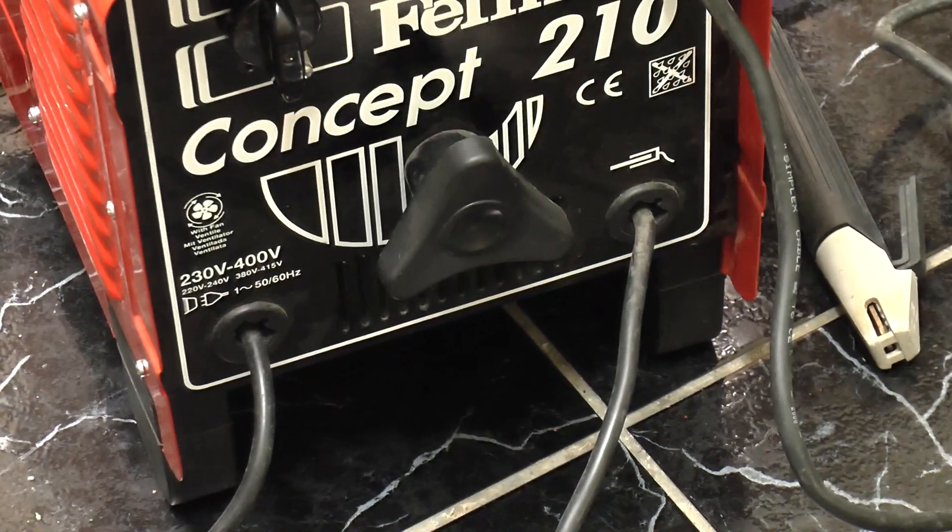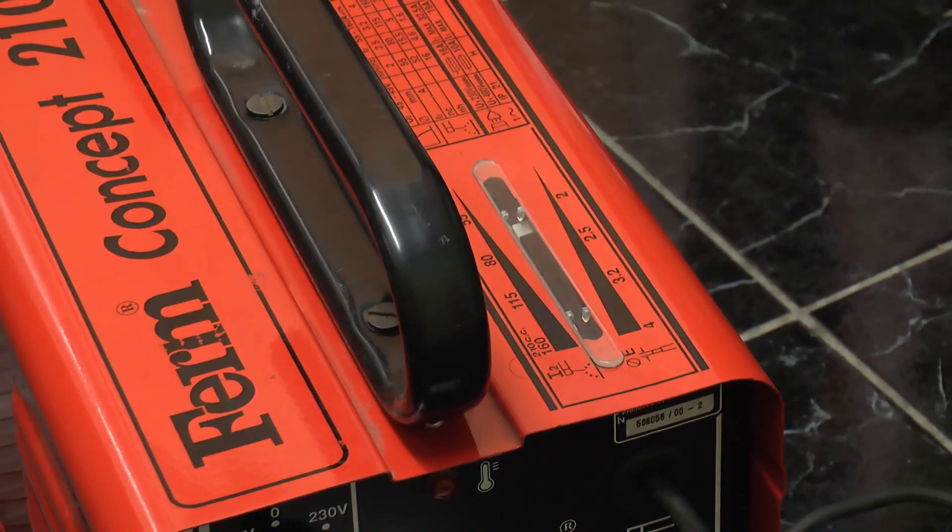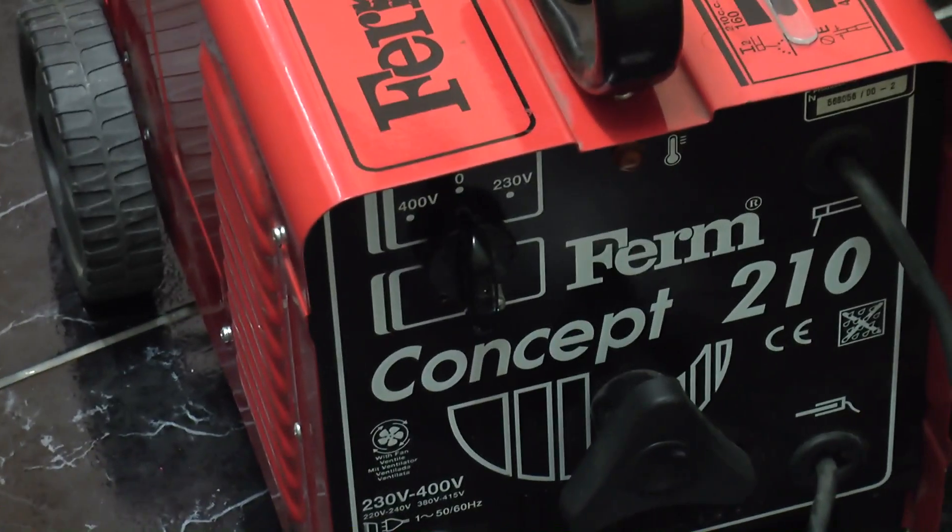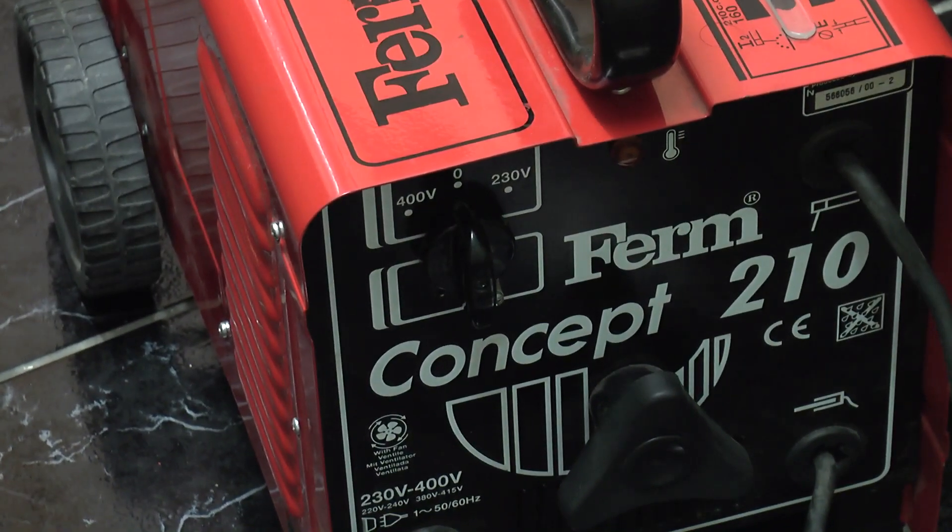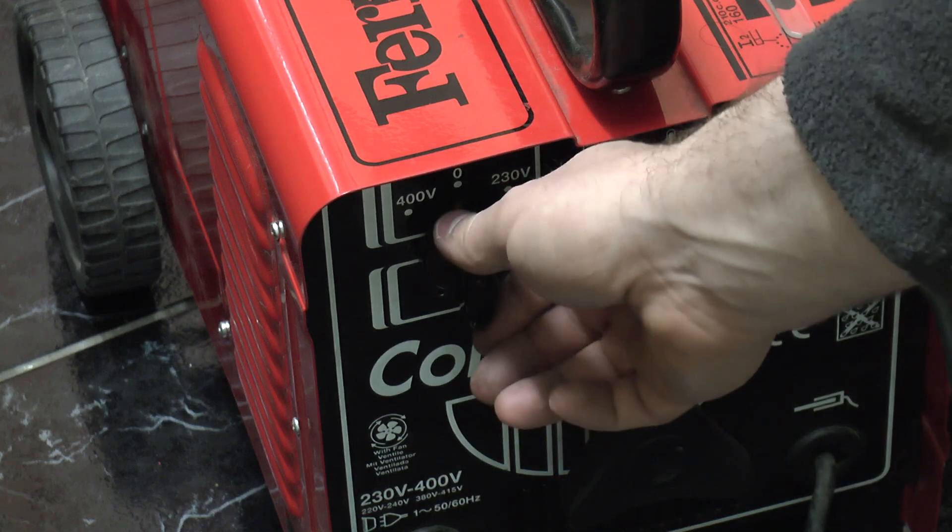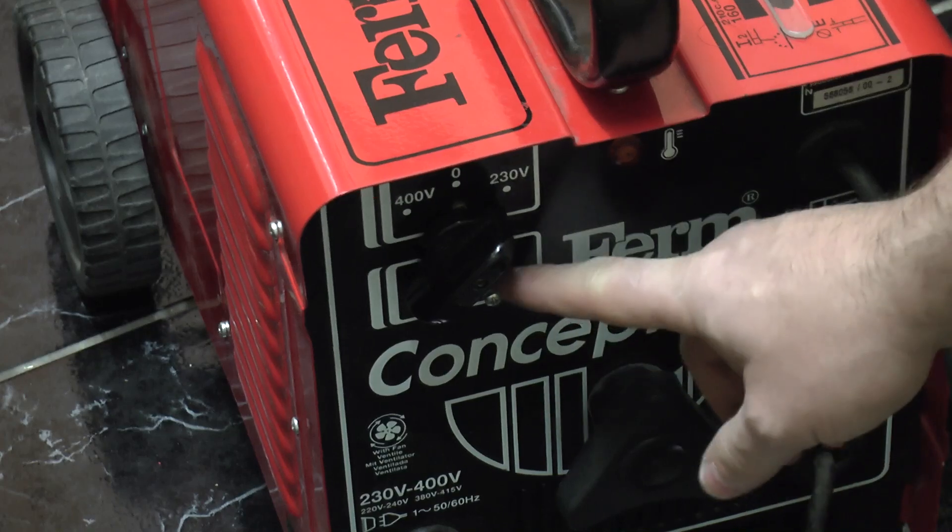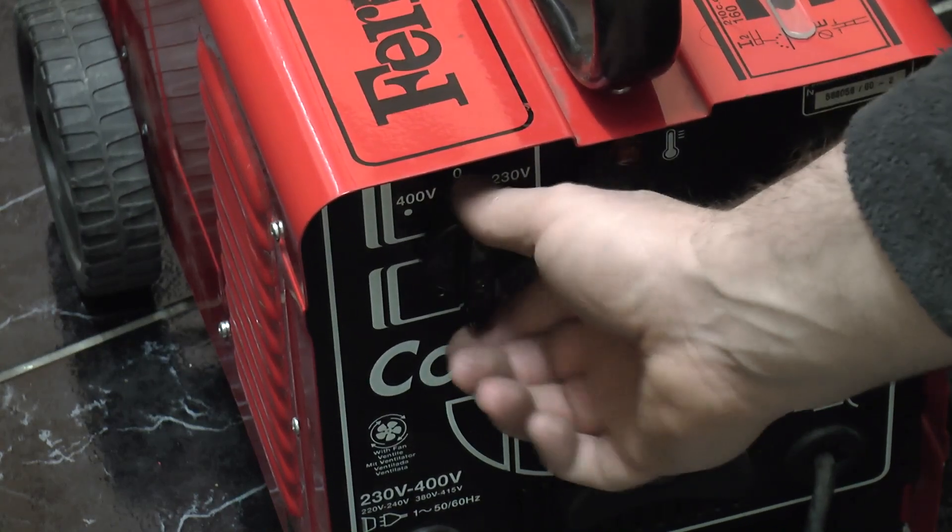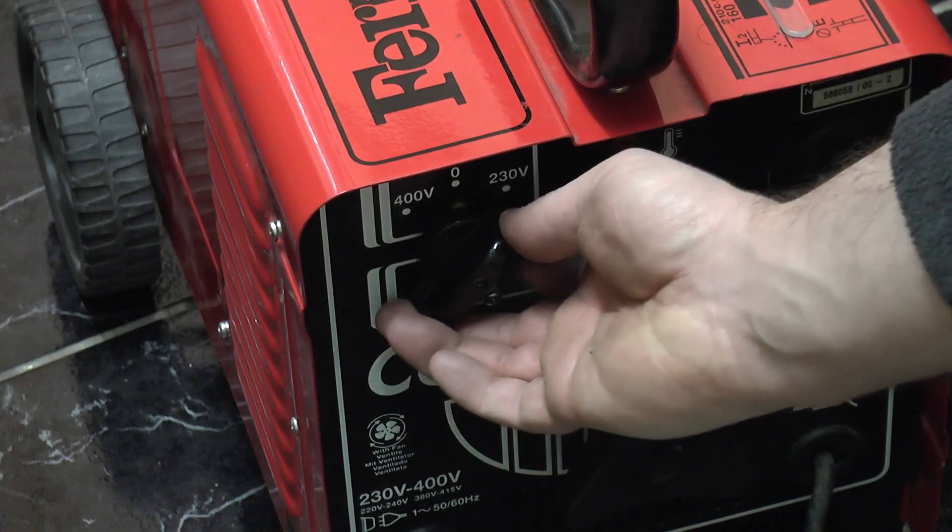In the middle we have a large hand wheel for adjusting the welding current, and on the top a sliding indicator which shows what that welding current is set to. A small screw is fitted at the front of the on/off switch so you can only select whichever voltage you've got it wired for. If you remove this screw and move it to the other side you can use it as a 400 volt welder instead, but as you can see at the moment it doesn't want to go there. Only on the 230.